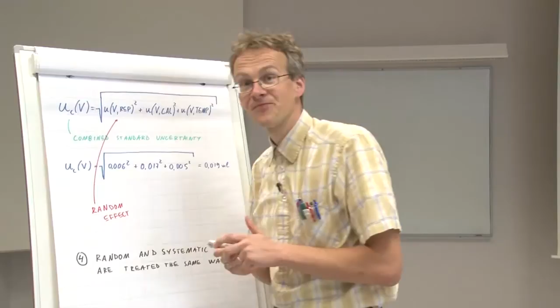Now, this calibration uncertainty, if we use the same pipette for the different pipetting operations, is a typical systematic uncertainty source. Because if the mark is a little bit off from 10 milliliters, then it remains off for all those pipetting operations. So that calibration effect is a typical systematic effect.